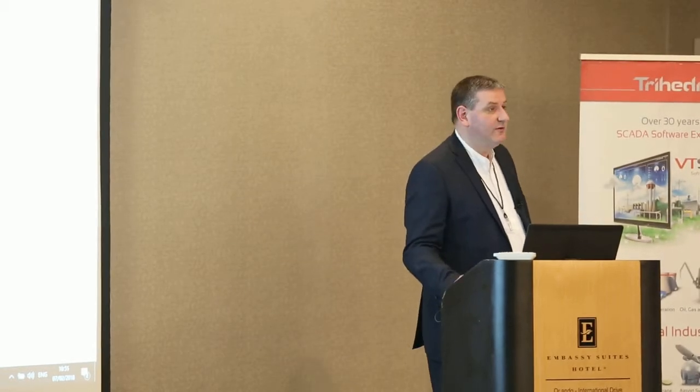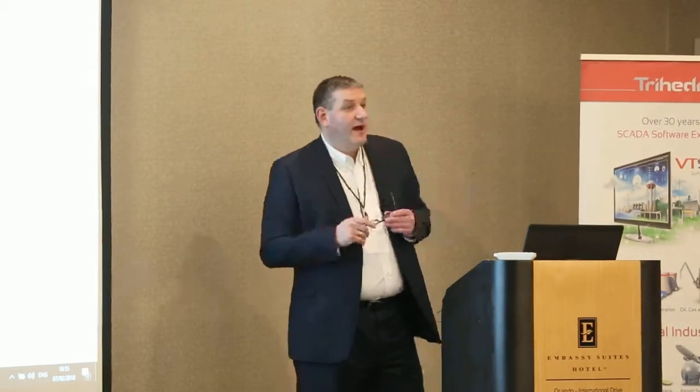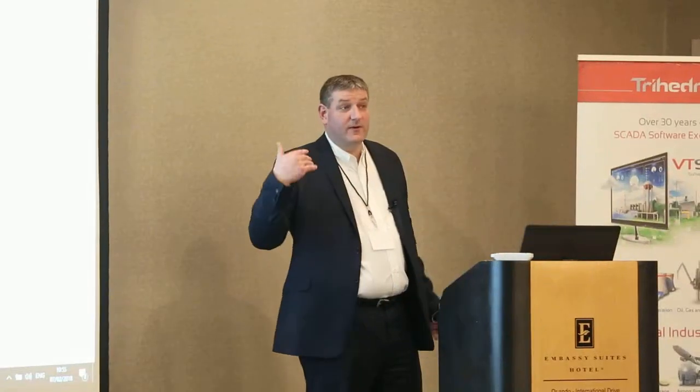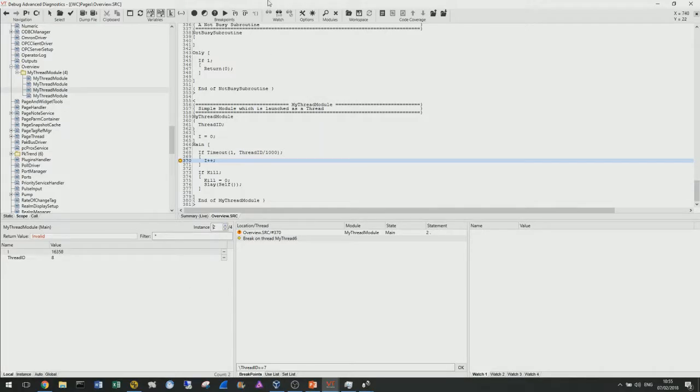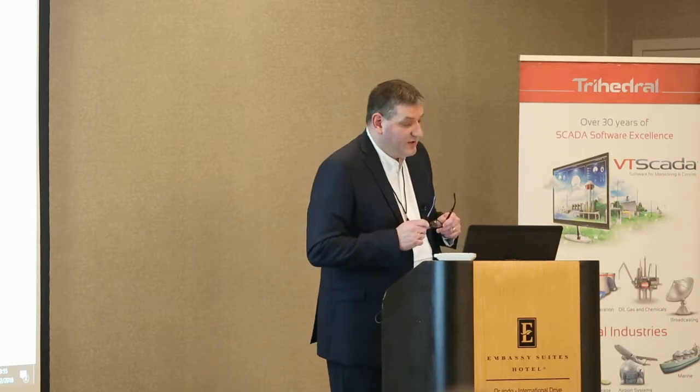Things like you can do \name equals and set it to the name of the tag, so you can find the name of a tag in a huge list, for example. It's really very useful for trying to nail down that one particular problem module that you have in trying to find it. Right. I should have pointed out just before I did that, but the breakpoint has a little question mark symbol in it when it becomes a conditional breakpoint. So you can identify that differently from a standard breakpoint.